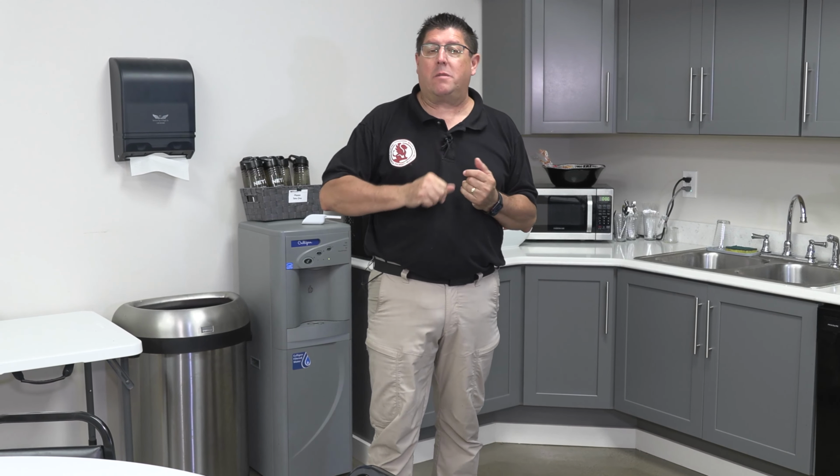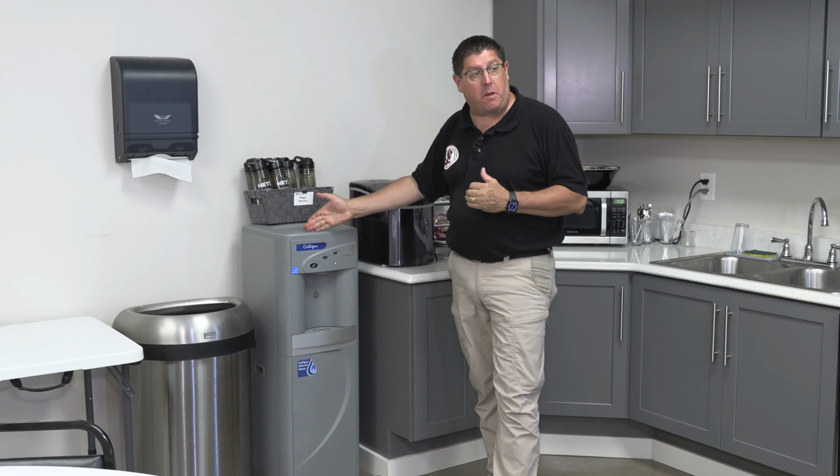We began talking about the plumbing in this building by first identifying where the plumbing came into the building. Then we talked about we need to identify whether it's public or private. Now, with a public water system, we talked about how it has to have a backflow preventer, and we showed that downstairs. The reason the backflow preventer is so important is so we don't contaminate the system, right? If anything happens. So these are two excellent examples I'm about to show you of why a backflow preventer is so important. We have a water dispensing system here.